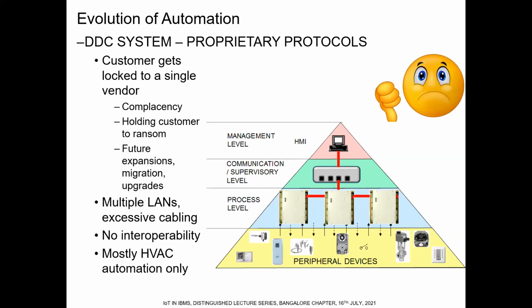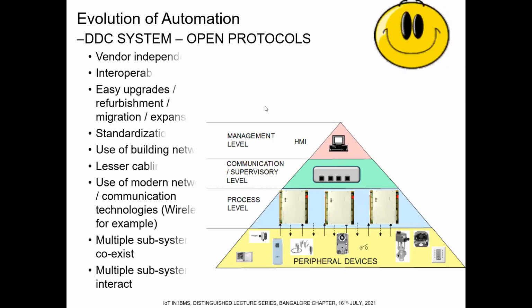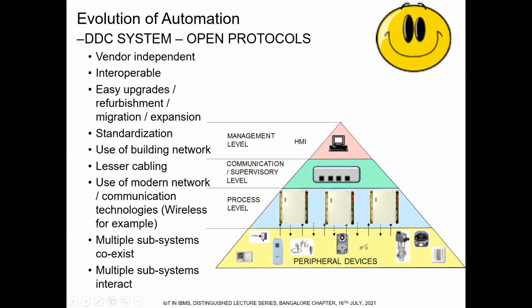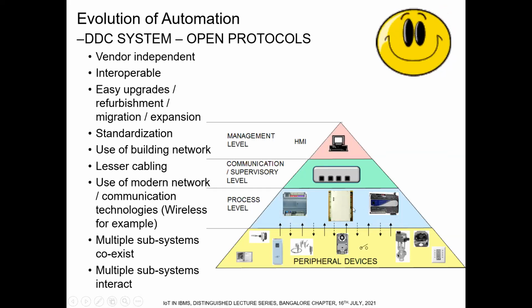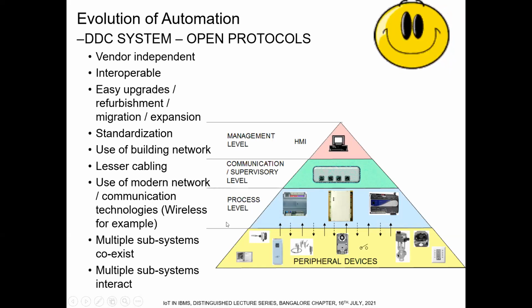Very sophisticated compared to those days, but when the evolution took place, this looked vendor dependent. This was not a very healthy system when network technology progressed inside the building. So what happened now is that the industry was forcing the controls and automation manufacturers to go for open protocols. That means these controllers, which looked similar, could be changed to different types of controllers because they could talk to each other. They did not talk only to the same type of controllers. These controllers had what we call BACnet, or open protocol.